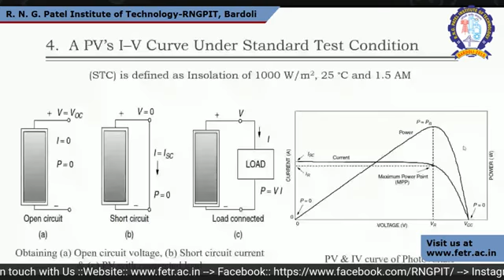The voltage at Pmax is 16.9, rated current is 7.1 ampere, open circuit voltage is 21.5 volt. Similarly, short circuit current is 7.45 ampere. So if we maintain this condition and short circuit this panel, we are able to get the value of 7.45. And with some mechanical dimensions, the module efficiency is 12.9%.